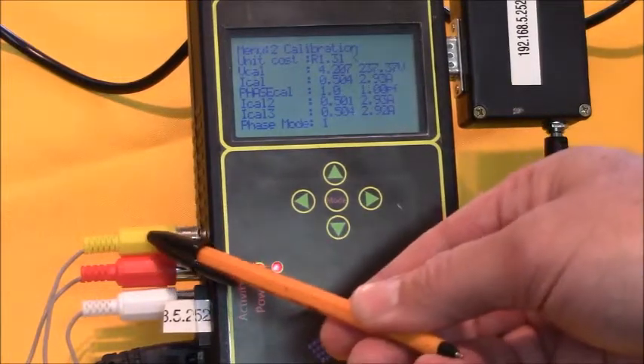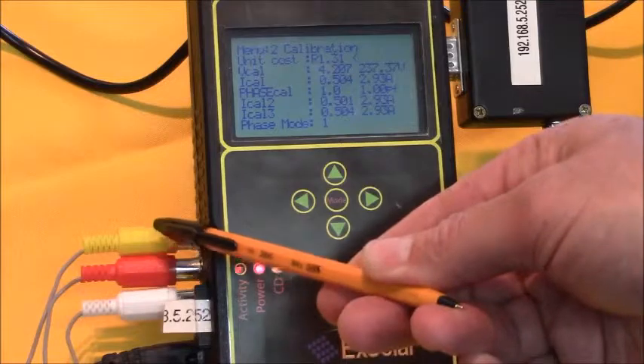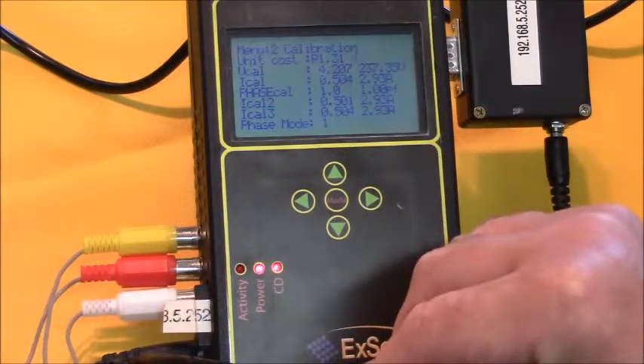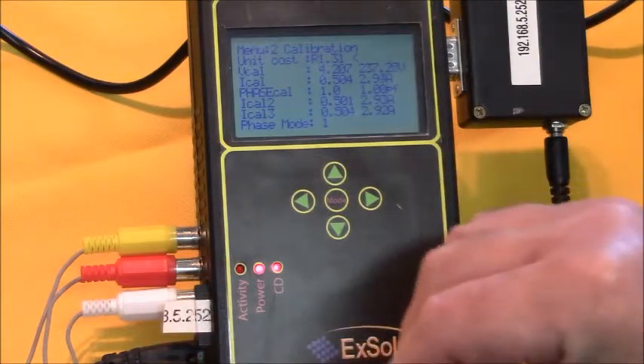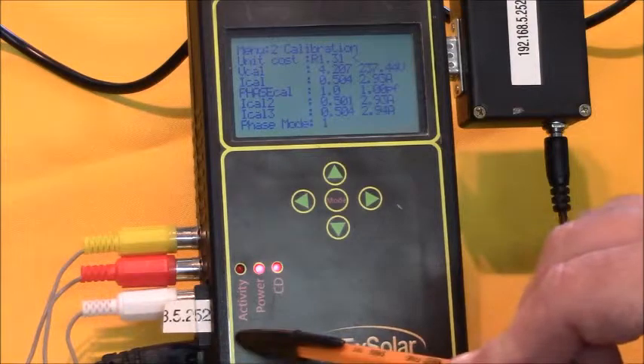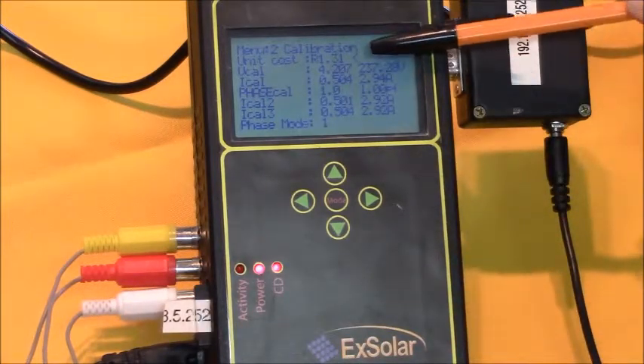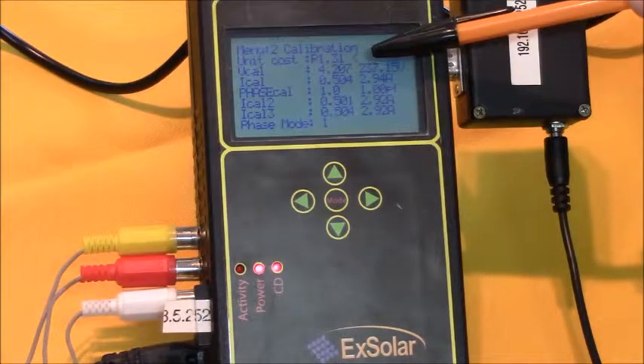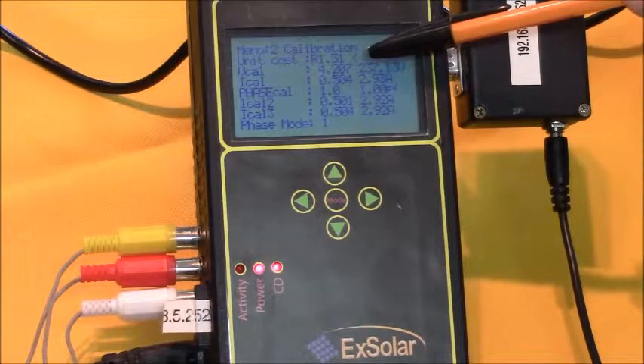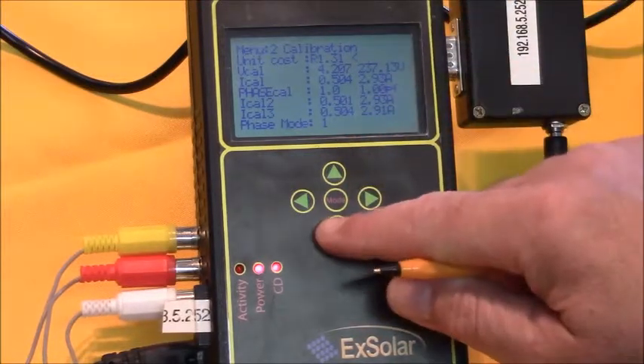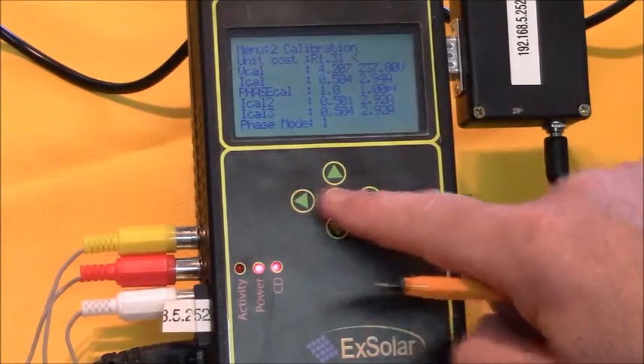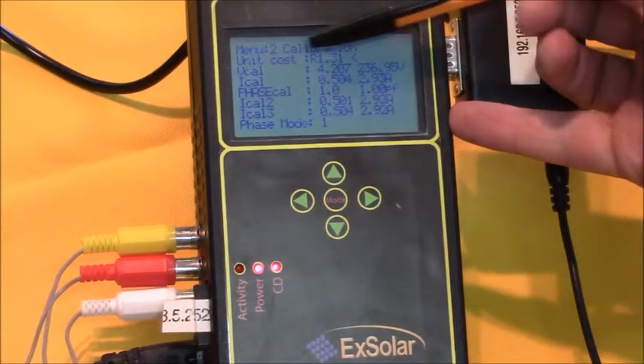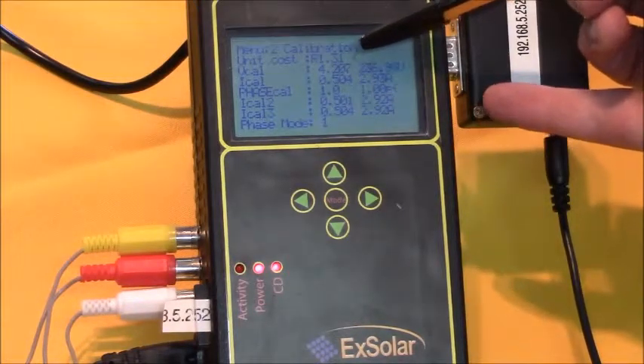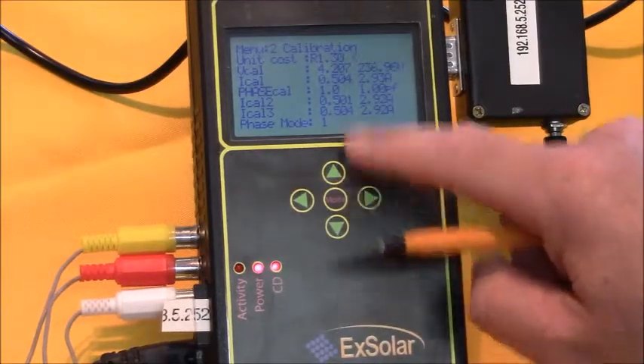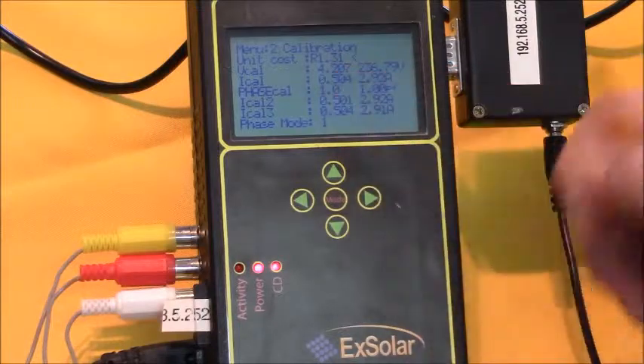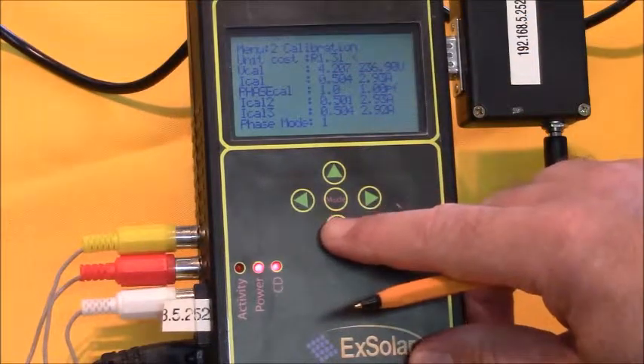The first sensor must be on the cable which is also the supply to the energy monitor, because the voltage is measured at this point of entry into the energy monitor. If you see on the screen there is a little arrow pointing to the left, that is the particular item which you are calibrating, and you move that arrow up and down using the up down arrow keys, and you change the value using the left right keys. So in this particular case, if you wanted to change the cost per kilowatt hour, you would use the left and right keys to change that value. And then move down to the next figure.